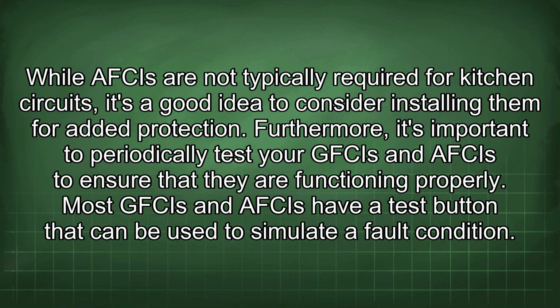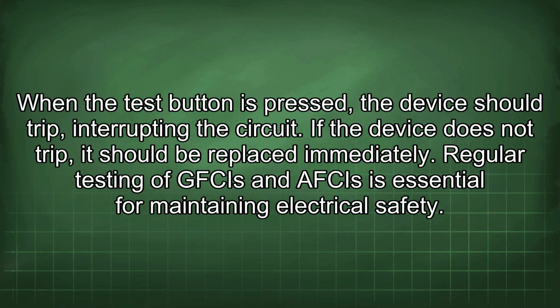Furthermore, it's important to periodically test your GFCIs and AFCIs to ensure that they're functioning properly. Most GFCIs and AFCIs have a test button that can be used to simulate a fault condition. When the test button is pressed, the device should trip, interrupting the circuit. If the device does not trip, it should be replaced immediately. Regular testing of GFCIs and AFCIs is essential for maintaining electrical safety.